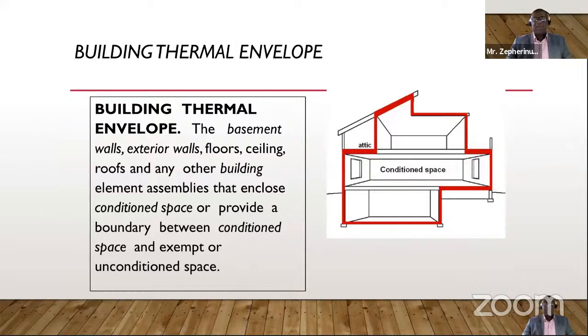So the building thermal envelope, this is the image on the right, gives you an idea of what the building envelope is, and all that is highlighted in red, you would have to demonstrate the requirements in terms of the R values, the U factors, and the solar heat gain coefficient of the building thermal envelope. What the code seeks to do is to ensure that the building is tight, number one, and number two, that the thermal resistance of the walls, the ceiling, the floors, and as well the thermal transmittance of the fenestration is tight. In essence, the conditioned space should not be affected by the hot temperatures on the outside. And the requirements for the thermal envelope are the minimum requirements, so that when you design your cooling system, the outside hot temperatures would not be able to penetrate the building as it would be where the envelope is not efficient.